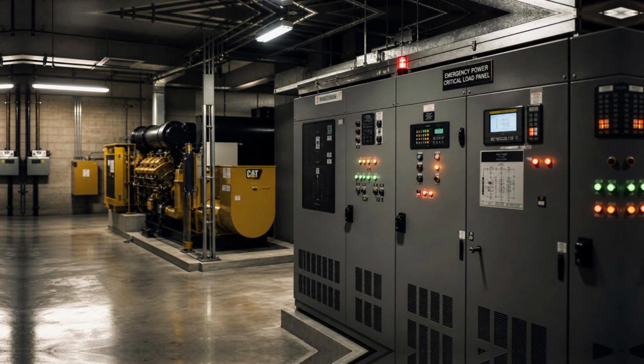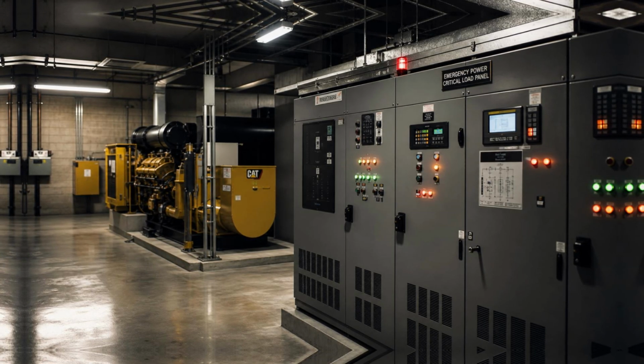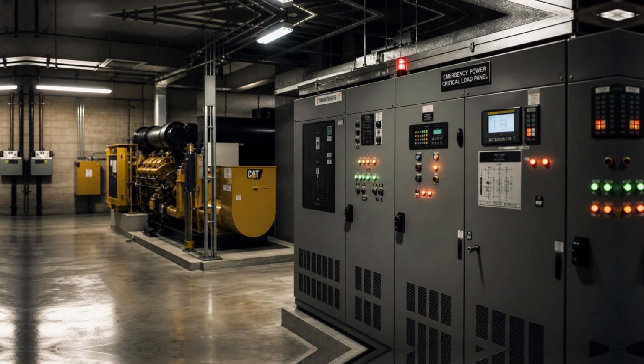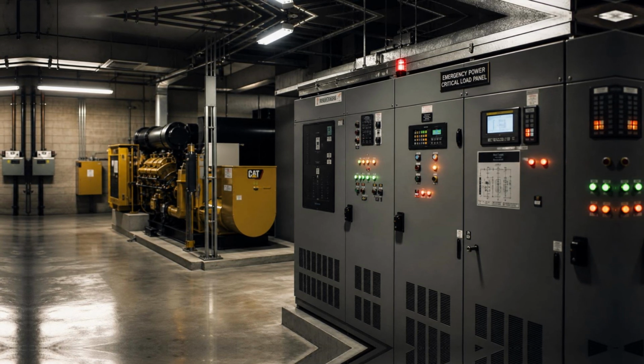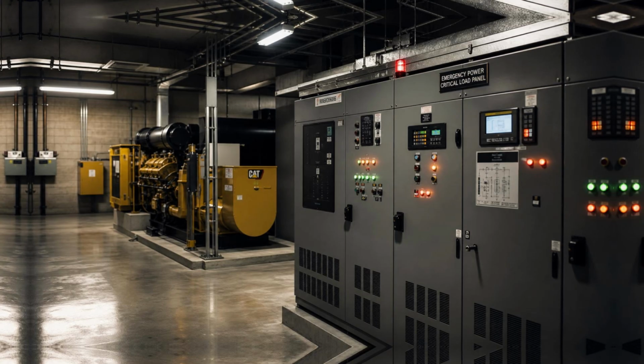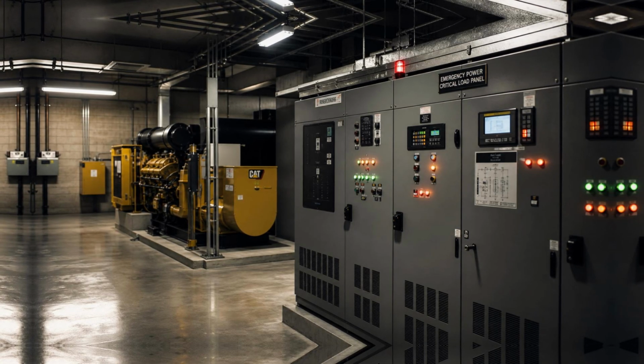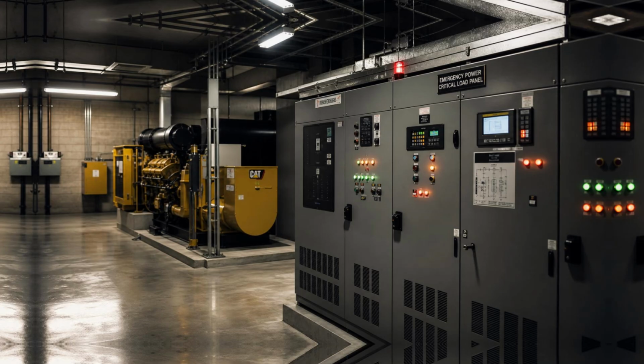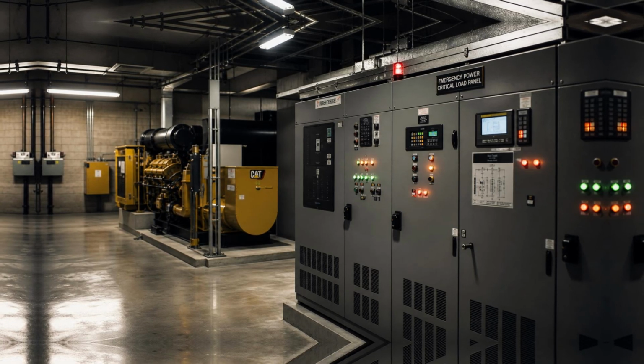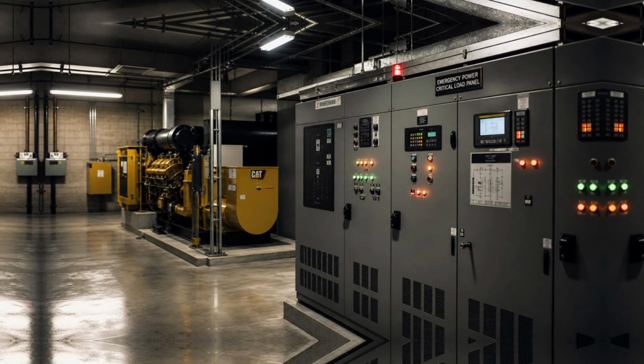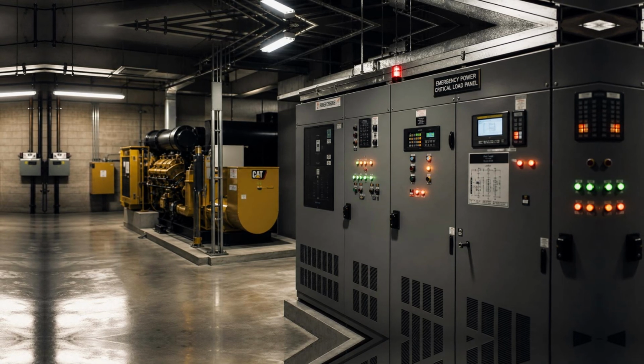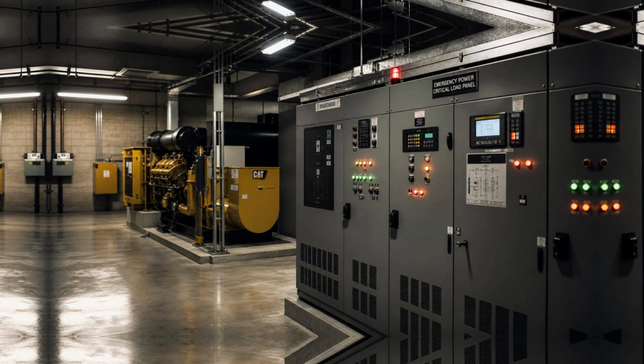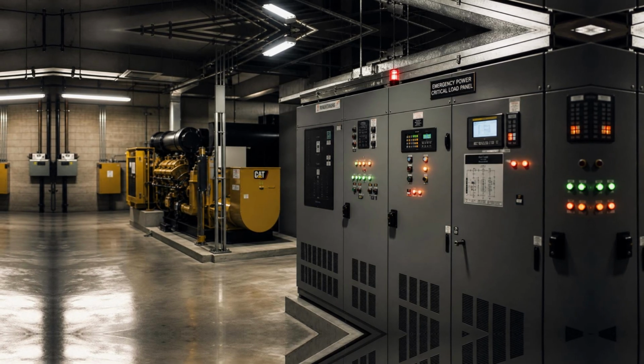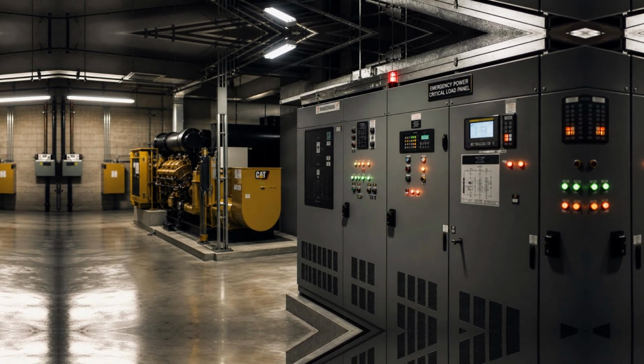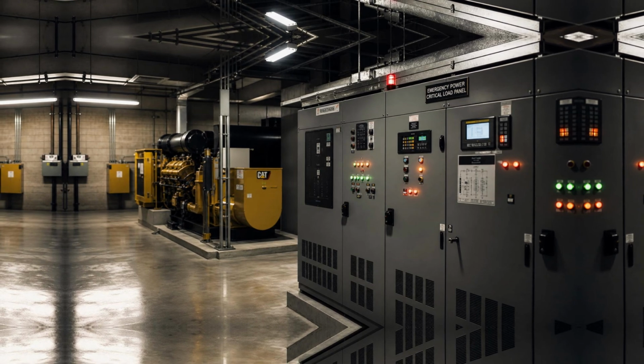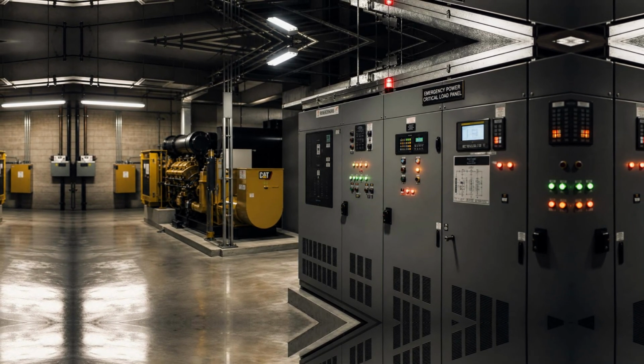Alongside the life safety branch, the hospital's emergency system includes a critical branch. The critical branch serves the equipment and the spaces where patient care is most intensive. Operating rooms, intensive care units, the recovery room, labor and delivery suites, the areas where patients are at their most vulnerable, where the monitoring and intervention equipment that sustains them is most essential, where any interruption in power could have immediate and direct consequences for clinical outcomes.